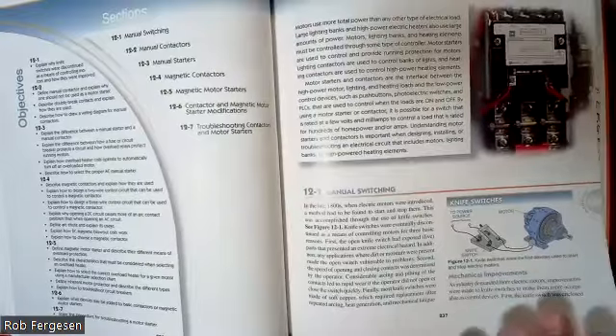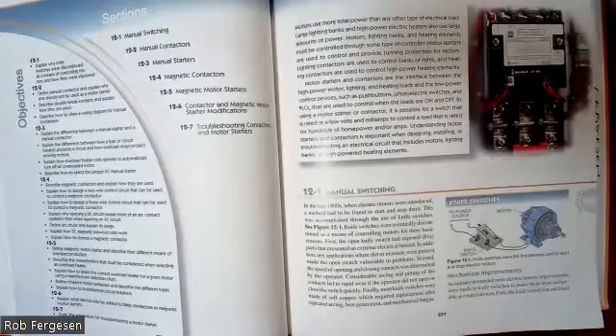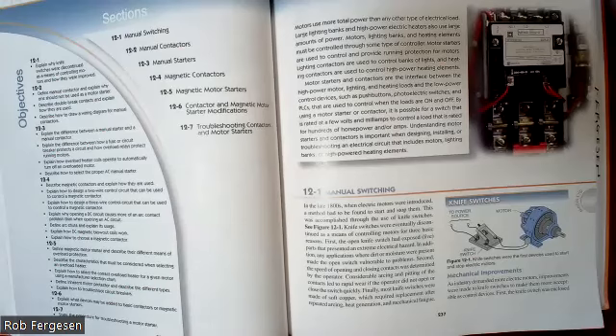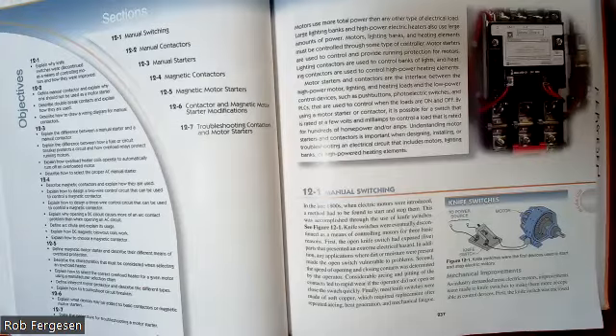So the book starts off with manual switching, as we do in our class, with the idea that manual means that an operator has to walk up to this switch, which contains this high power. He has to walk right up to a panel, which inside that panel will be the three-phase power that's going to run his motor or his electric heater or whatever he's going to turn on or off. He needs to walk up to that switch and physically change its conditions.